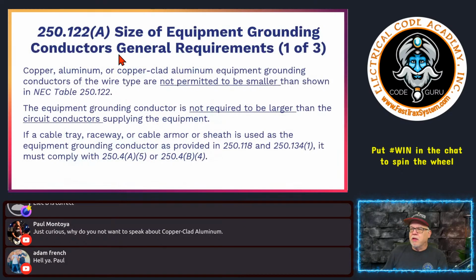Okay. Sizing of the equipment grounding conductor. We're going to knock this part out today, and hopefully we'll be good enough done with this. So whether you have copper, aluminum, or this other type of conductor, equipment grounding conductors of the wire type are not permitted to be smaller. So they can't be smaller. Could they be larger? Yes. Voltage drop or an engineer could demand them being larger. But they're not to be smaller than what's stated in Table 250.122.